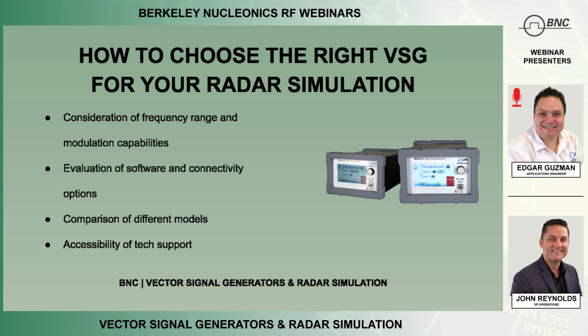And we do get a lot of questions about how to connect a VSG or signal generator into your system. So you have a very large testing system, and you want to be able to integrate a unit into your system. So how well the software and the remote communications work is also a very large factor, considering these units a lot of the times will go into manufacturing systems. So they're integrated into a massive complex system, and they need to be able to be easily interfaced with the rest of the other instrumentation via software.